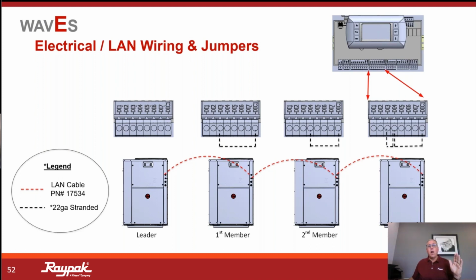Okay, so that's step one. Step two, and to Sanan's point, is we now also need these jumpers that are field installed to identify the unit where it is in the sequence, whether it's the second, third, or fourth unit. Does that make sense? Yes, it does. So it's a combination of the interconnection of the daisy chain wiring as well as the jumpers that is going to give us that ability to communicate amongst all units.